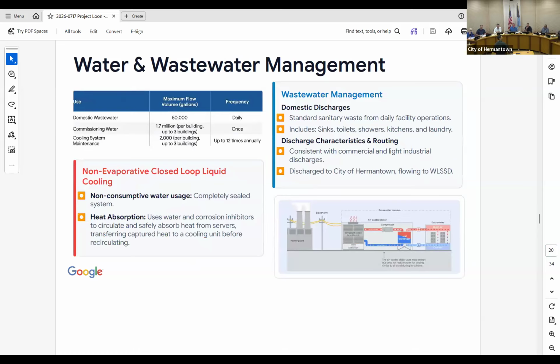For water and wastewater management, this project is a non-evaporative cooled data center, meaning water will not be used to consumptively cool the data center site. Within the AUAR, we identified the anticipated flows required for the project, consistent with today's design of a 3 data center building campus, with domestic wastewater at 50,000 gallons a day. That would be for standard commercial domestic uses: sinks, toilets, showers, kitchens, anything needed for a typical commercial development project or campus.